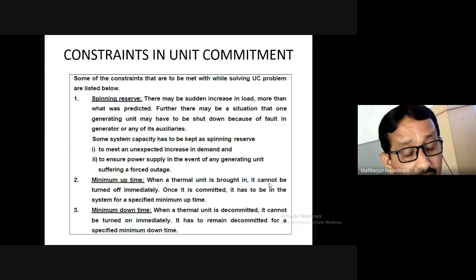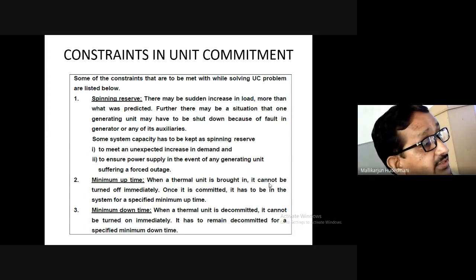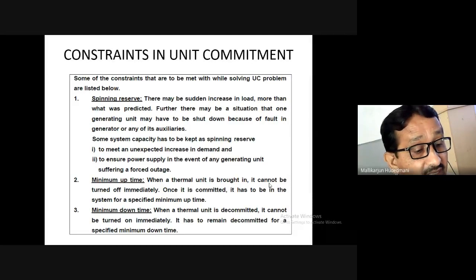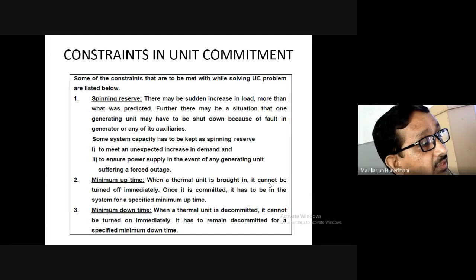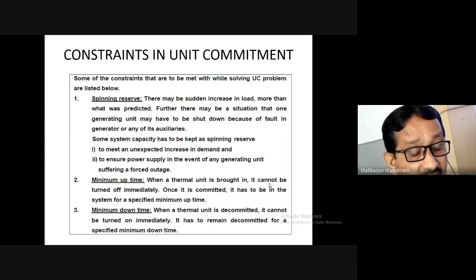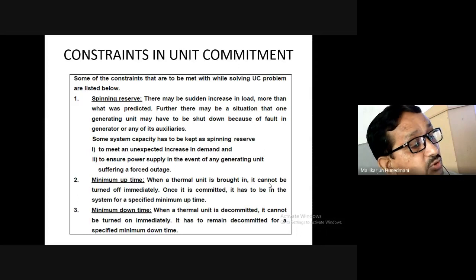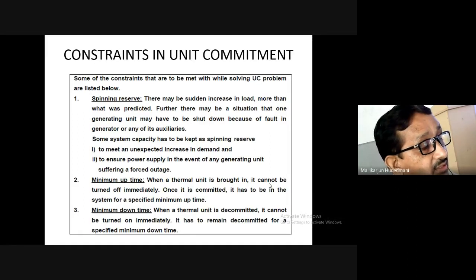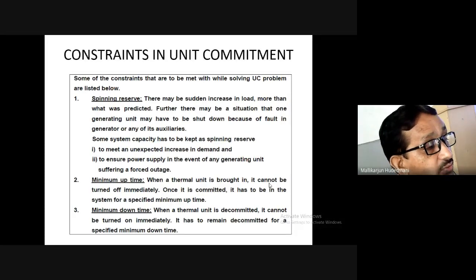In line with which, we have some important constraints identified under the unit commitment schedule. The first one is spinning reserve. As the name says, it is a reserve of excess generated energy in the power system, readily available to extract to meet unexpected, contingent, sudden changes in the load absorption. It is an excess generation. Suppose we have 5 generators generating a certain amount which is in excess to the actual requirement and losses.